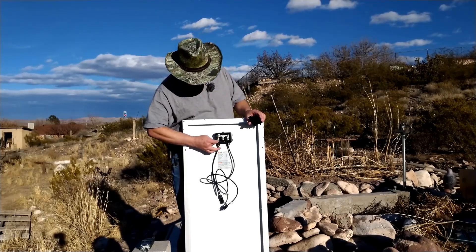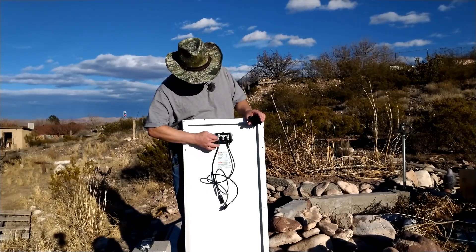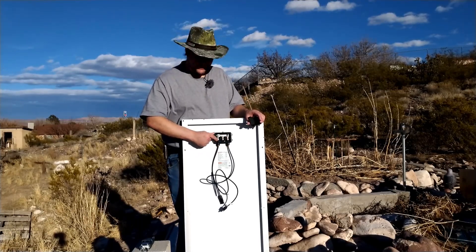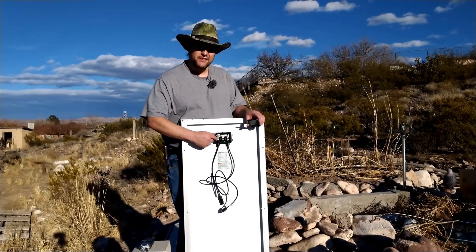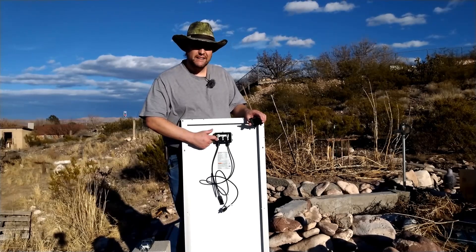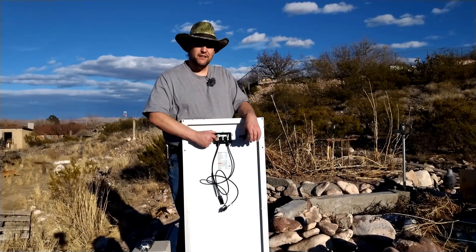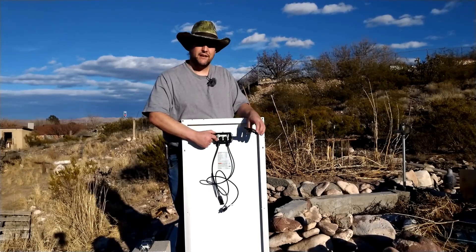The only thing I don't like is the wires are screwed in here, and they didn't really do the best job on the connections. I'm going to unscrew these, straighten up the wire, and put it back together — probably with a little bit of anti-oxidation compound to make certain that the connection lasts and works really well.